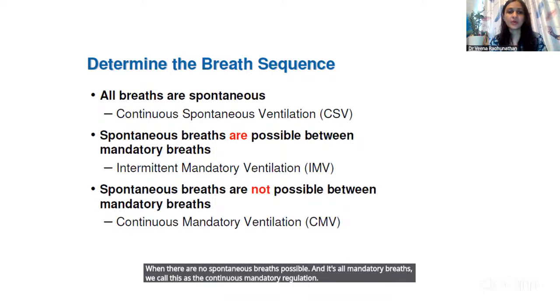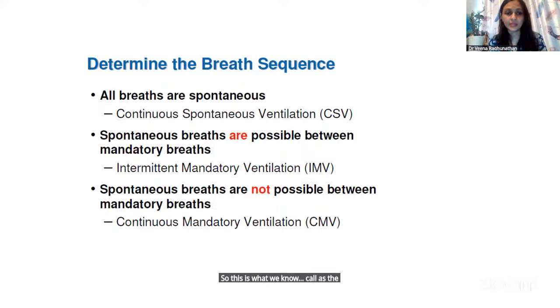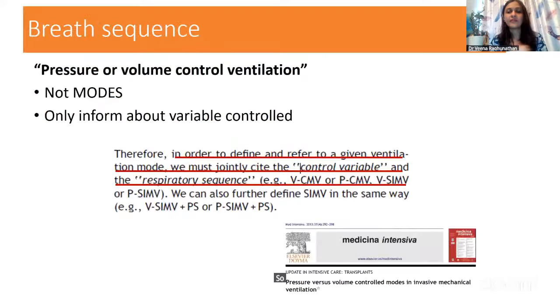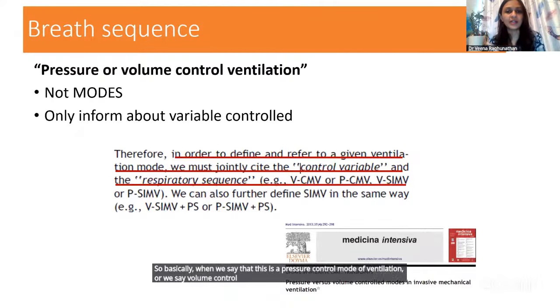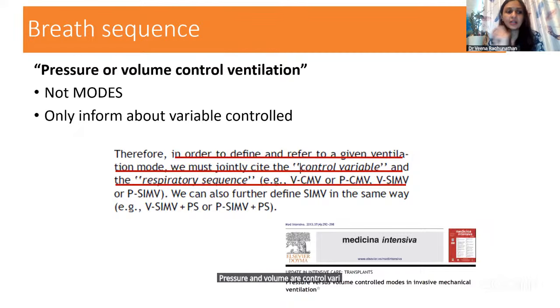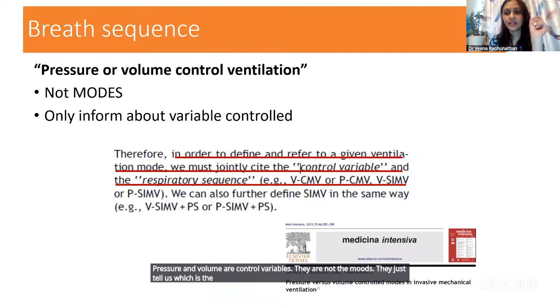So this is what we call the breath sequence. When we say that this is a pressure control mode of ventilation, or a volume control mode of ventilation, it is wrong terminology. Pressure and volume are control variables. They are not the modes. They just tell us which is the constant variable that we have set.